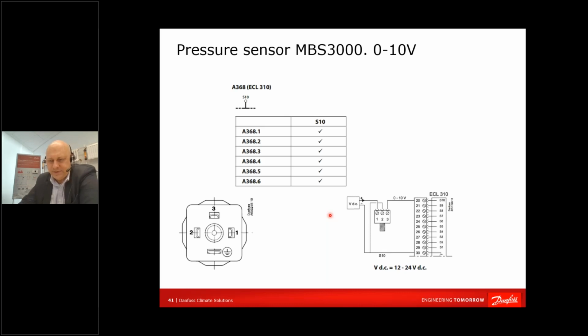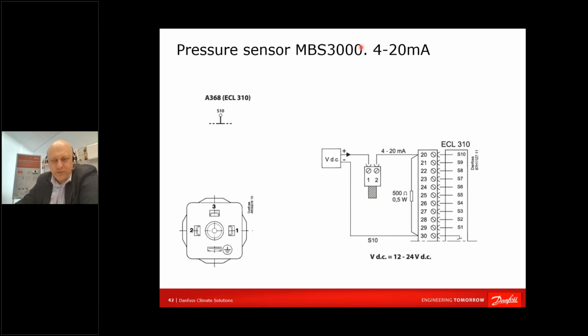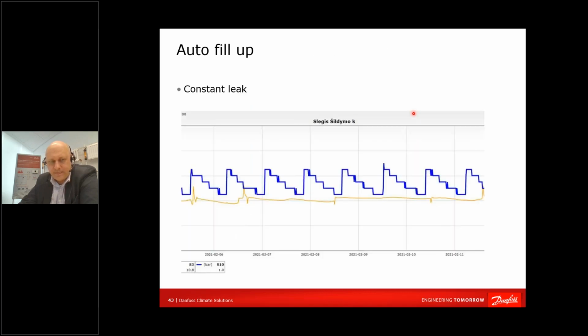Then you will need some settings in the ECL to adapt the range of the pressure sensor, so the ECL reads values correctly. If you decide to use a 4 to 20 milliamp pressure sensor, you will have to install a resistor of 500 ohms and 0.5 watts. If you do not do it, something bad will happen. The ECL will be damaged, so you have to install that resistor.